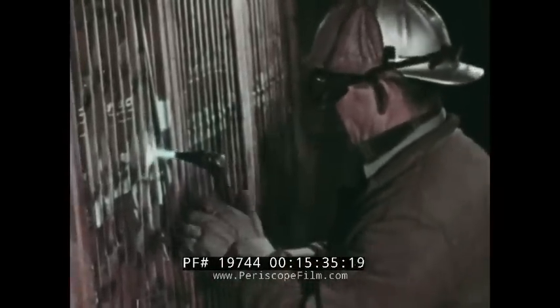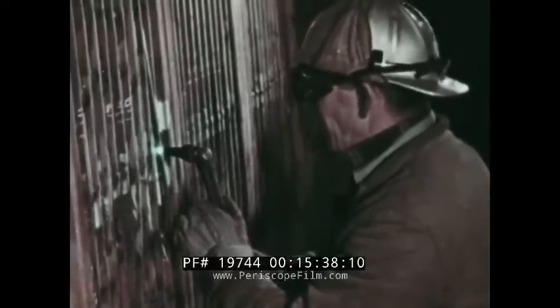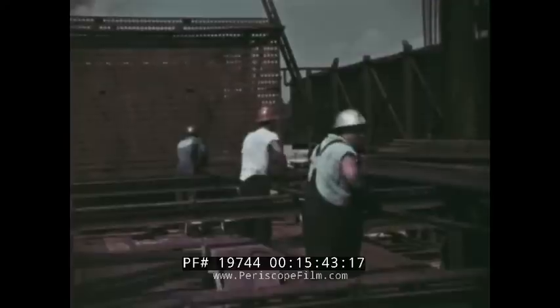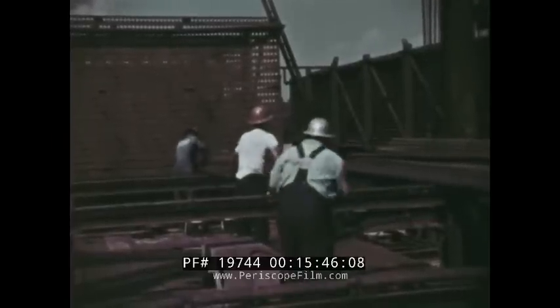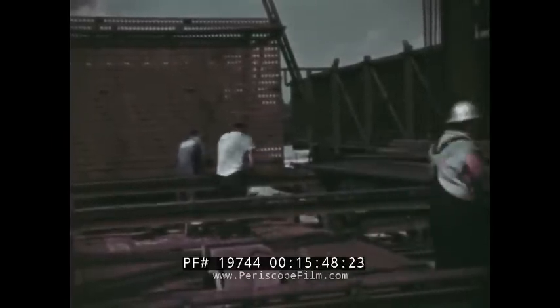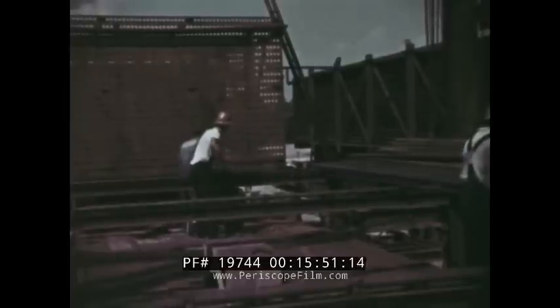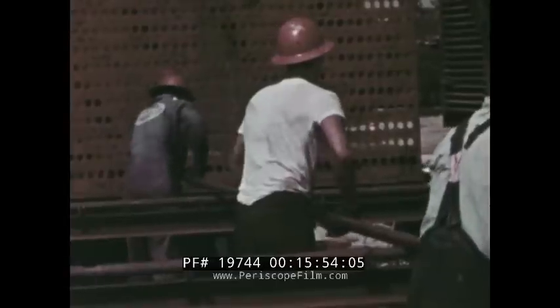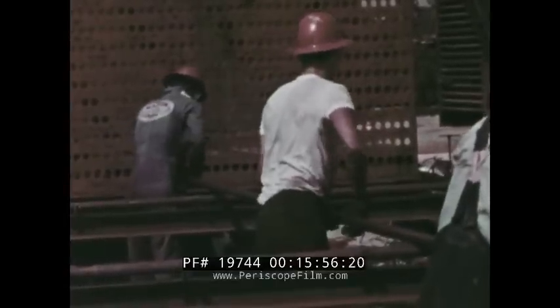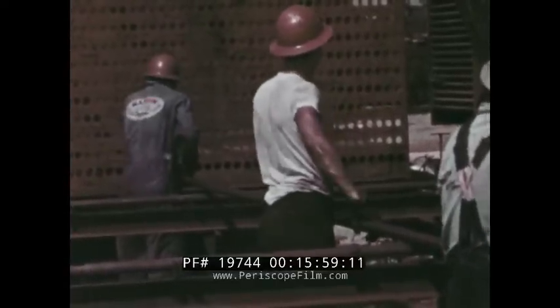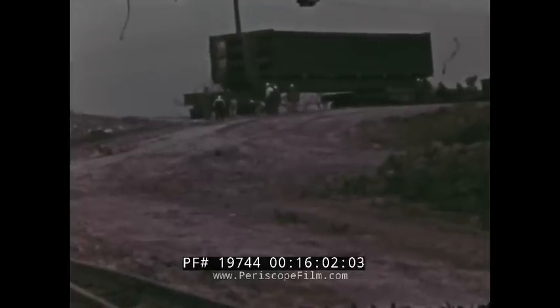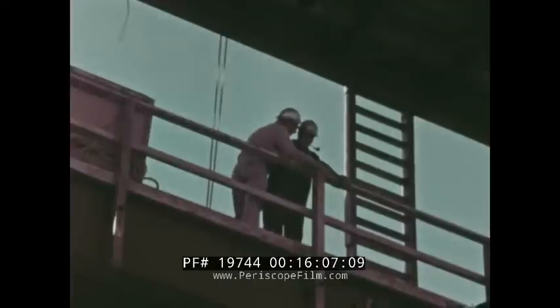Furnace walls are membrane constructed, 1-inch tubes with 1/4-inch steel bars welded between to form a continuous gas-tight wall. A novel construction technique worked out on the job was the erection of the air preheaters. These giant assemblies, made of 2-inch tubing, form a structure about the size of a 10-story building. Normally, the assembly of these sections would take place high above ground. Engineers at the site devised methods of putting them together at ground level and raising them into place in great 90-ton sections.